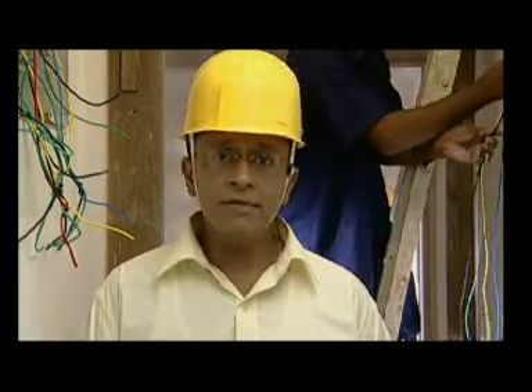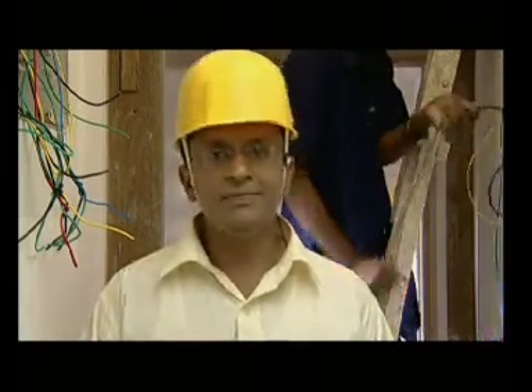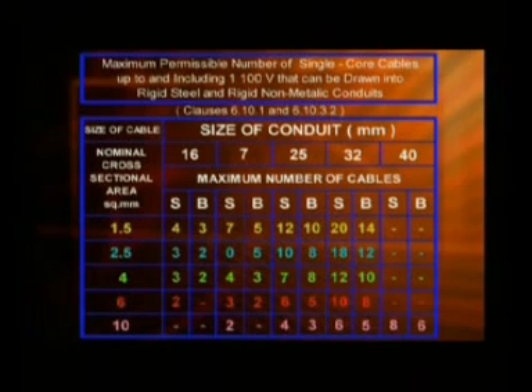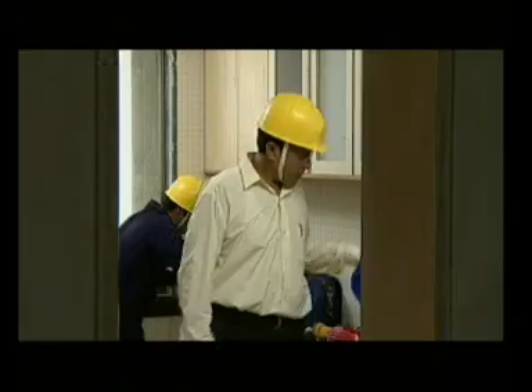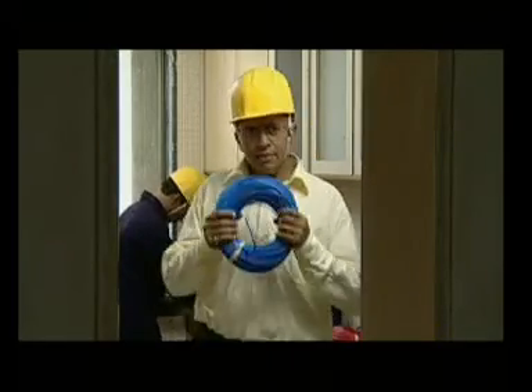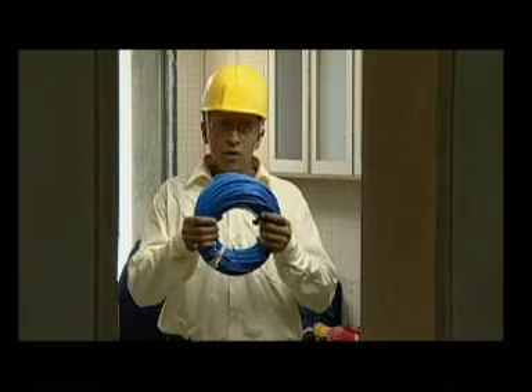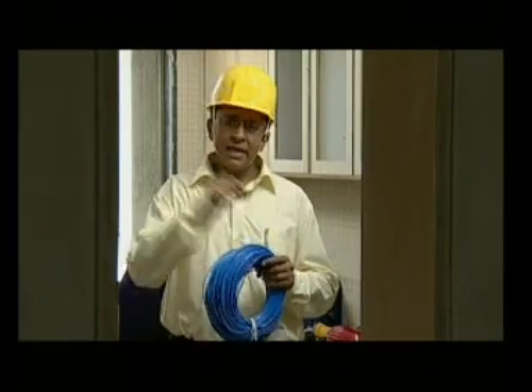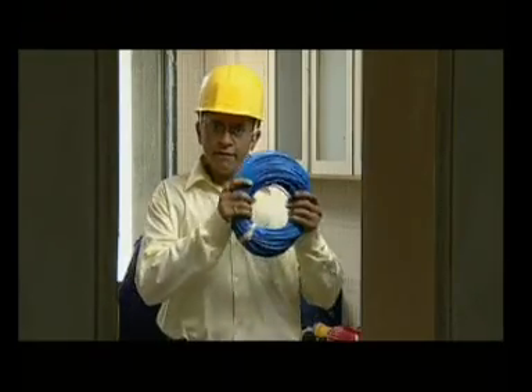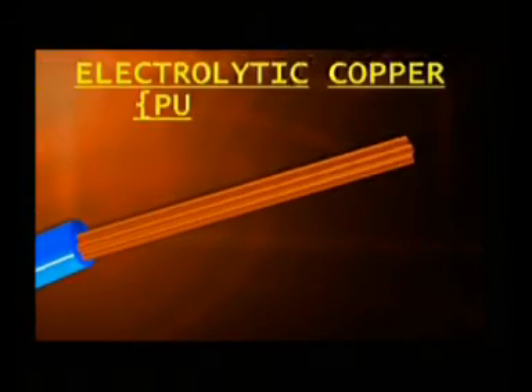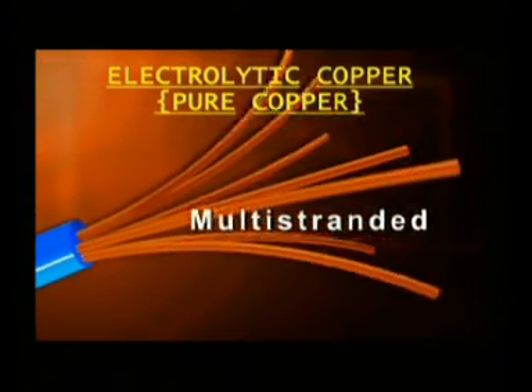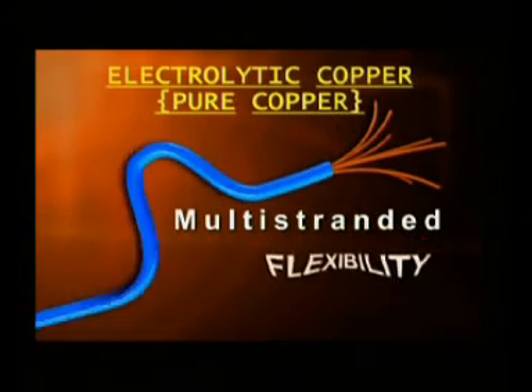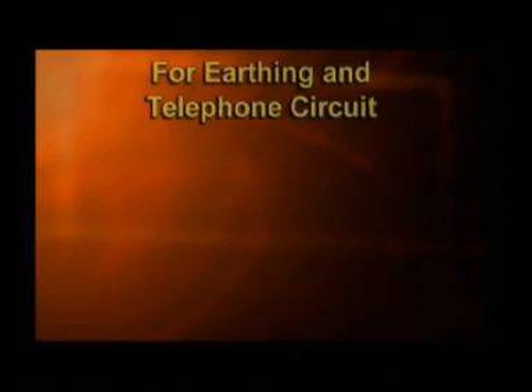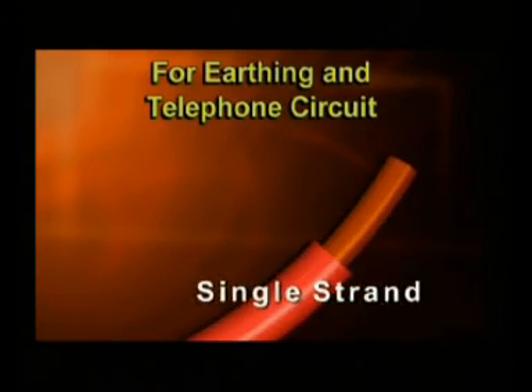Wherever the wiring has to be given a turn, make use of a rectangular bend to prevent any damage. For this, IS 732, Section 2, 1983 should be read and fully understood. When you refer to IS 732, you will learn how many cables of any given size can be inserted in a particular conduit. You must remember, wires are always bent, they are coiled up and they are tied, and then pulled through conduit pipes. Therefore, these wires must be extremely flexible. Always go in for multi-stranded electrolytic copper wires, which are both stronger and more flexible. However, for earthing and telephone circuits, you can make use of single-strand wire.